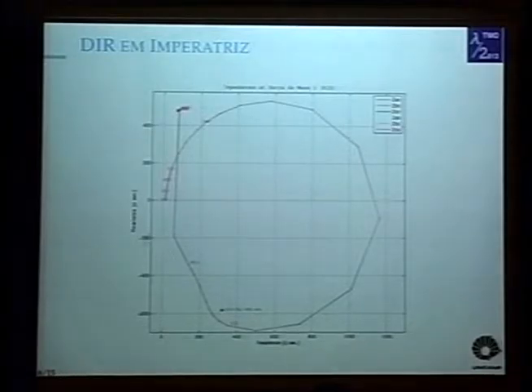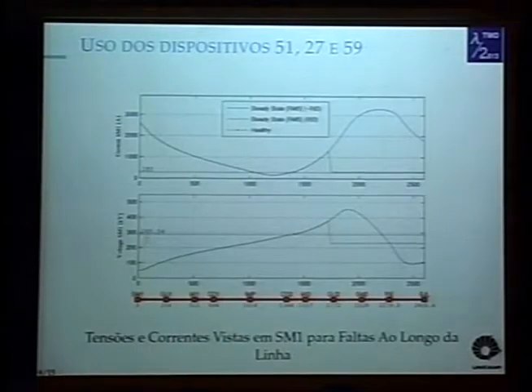The reduced insulation distance put in Imperatriz changed the impedances we found in Serra da Mesa 1 for faults happening in the end segment of the line. When you have a fault in the end segment of the line, the impedances that we found here skip to this other point more above. So if we try to design a protection system, we need to take into consideration this behavior of these impedances. We need to take the reduced insulation distance into consideration.